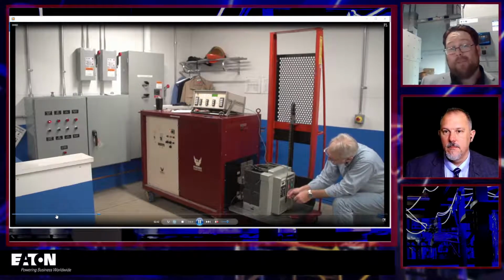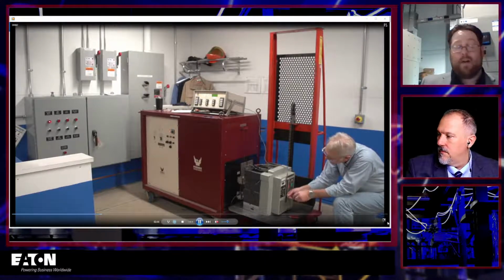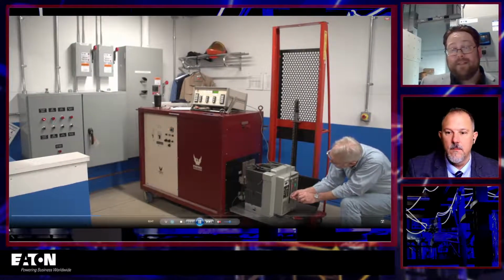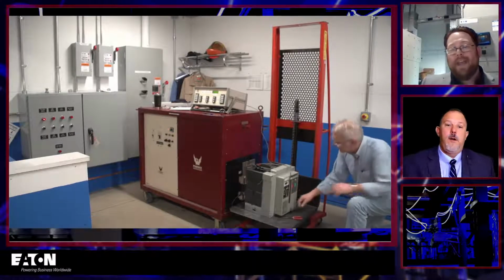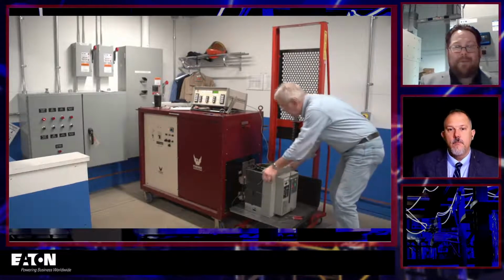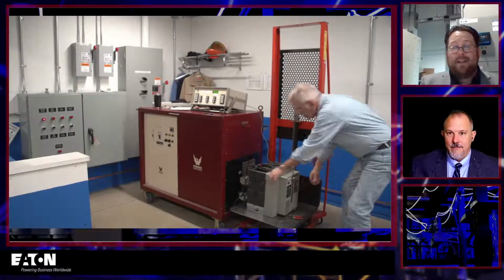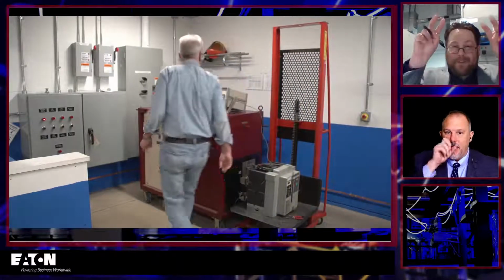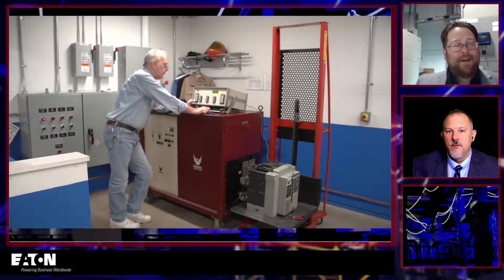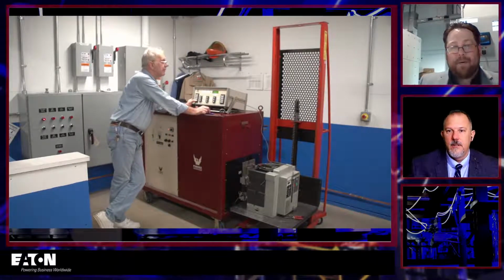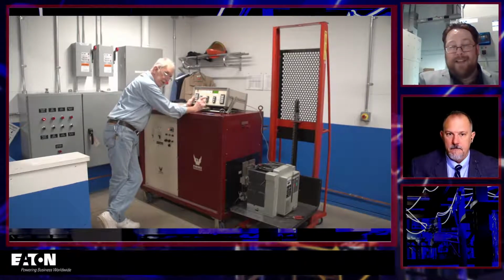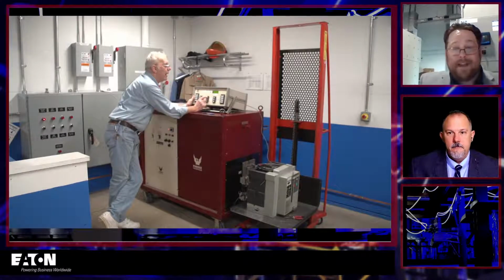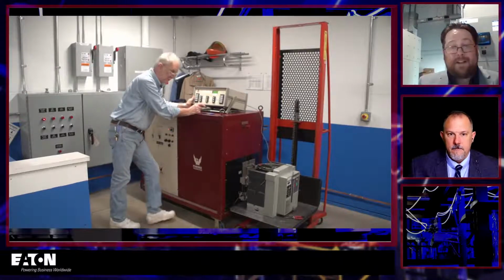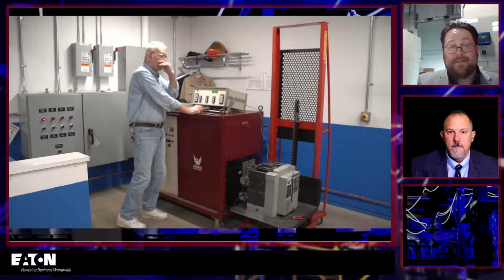But you were saying about how much it weighs. That test set is probably easily 1,000 pounds that you're taking to your equipment, right? And in this environment, we're just testing a breaker. In the real world, I'm going to do air quotes here, the real world, we're having to disconnect those cables from the transformer, and maybe they're just a braided cable, so that's relatively easy. And we're going to attach cables to the output of this test set and wire those 500 MCM cables, 750 MCM, etc., into the gear to do the test.